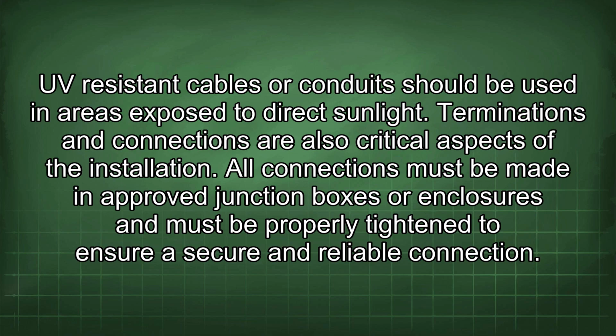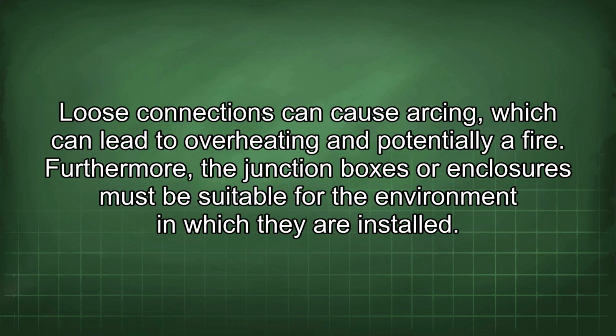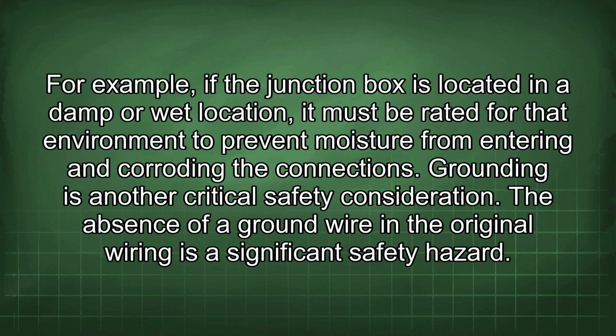All connections must be made in approved junction boxes or enclosures and must be properly tightened to ensure a secure and reliable connection. Loose connections can cause arcing, which can lead to overheating and potentially a fire. Furthermore, the junction boxes or enclosures must be suitable for the environment in which they are installed. For example, if the junction box is located in a damp or wet location, it must be rated for that environment to prevent moisture from entering and corroding the connections.